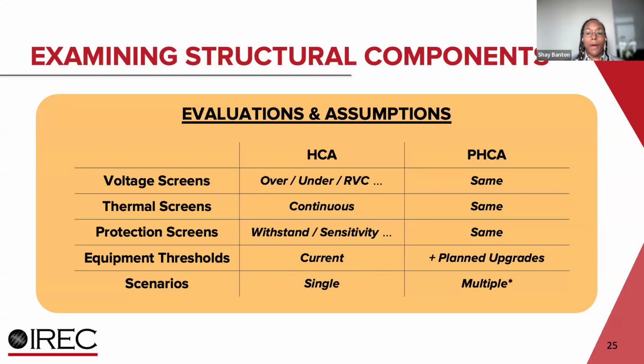You're really focused in host capacity on continuous ratings of equipment. For the engineers and non-engineers here, continuous just means how much wires can accommodate under normal circumstances, day to day. Then there are other settings like emergency or withstand ratings, based on fault conditions or abnormal conditions, which you don't really want to design the DER penetration levels based on these very short-term limits. You want to focus on the long-term ability of equipment to accommodate those systems and the current they're outputting. So for PHCA, you're going to use that same continuous rating.